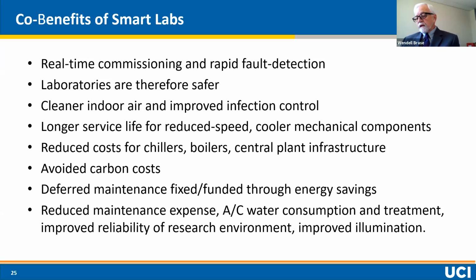Indoor air quality and improved infection control are, again, two sides of the same coin. The fact is, most pathogens are hitchhikers - they travel on particulates. We've been able to slow down air changes, and therefore the air speeds coming through fans and filtration media, by about half. That means our standard filter is now a MERV 14, which is one notch below a HEPA filter. That is a safer infection control environment.